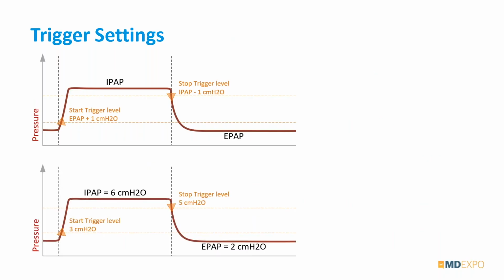And let's say you have a BiPAP ventilator and you have to test that. The first settings that they ask you to use is an IPAP of 6 and an EPAP of 2. So then we can tell our gas flow analyzer, okay, use the pressure waveform, and a start of an inspiration phase is when it crosses the 3 centimeters of water pressure line on a rising edge, and a stop trigger if it drops below 5. So that will allow us to trigger here, right?